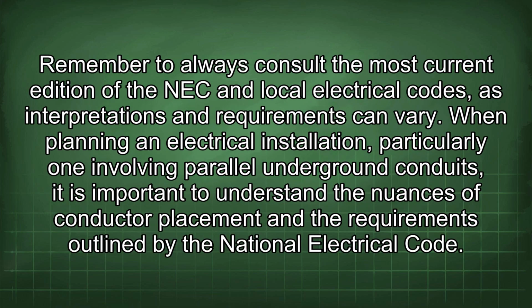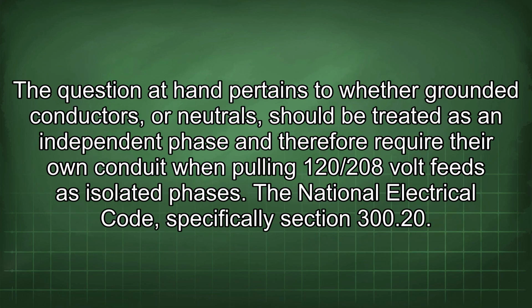Remember to always consult the most current edition of the NEC and local electrical codes, as interpretations and requirements can vary. When planning an electrical installation, particularly one involving parallel underground conduits, it is important to understand the nuances of conductor placement and the requirements outlined by the National Electrical Code. The question at hand pertains to whether grounded conductors, or neutrals, should be treated as an independent phase and therefore require their own conduit when pulling 120/208 volt feeds as isolated phases.